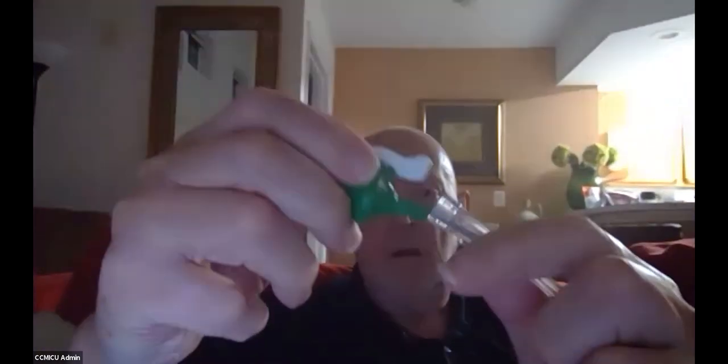What this is for, okay, you must be transferring to another station. So this is for feeding our nebulizer, and this is the first big change: our nebulizer, not the CPAP. You put the other end of the neb hose onto this stab, and then you would close the valve, or you'd probably screw it on first.